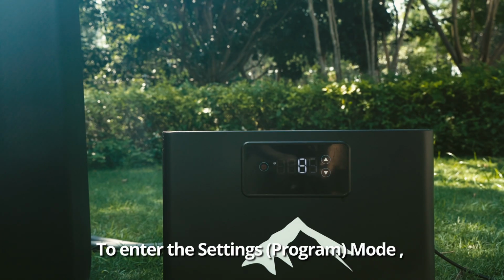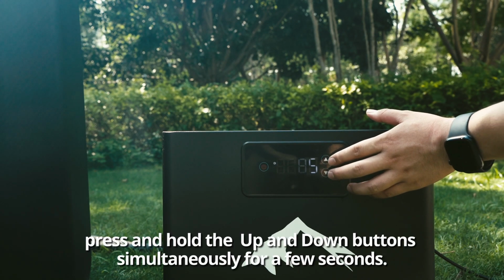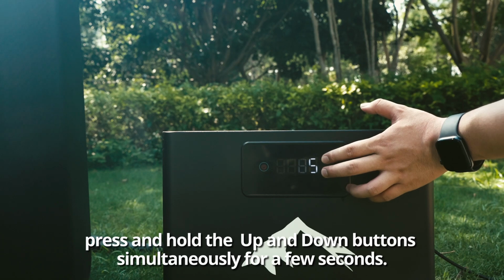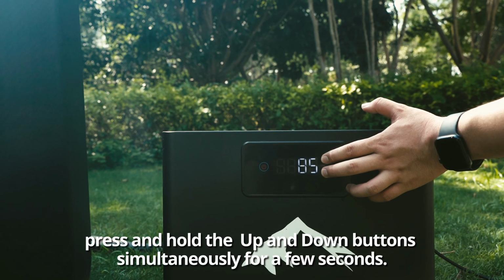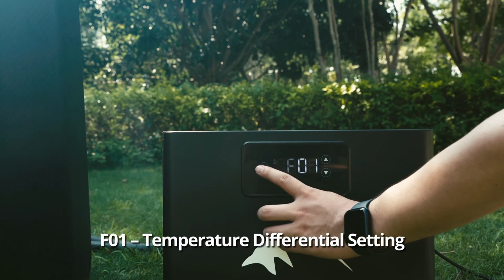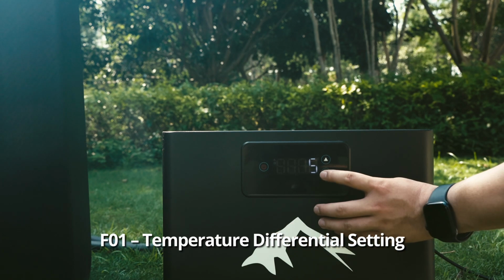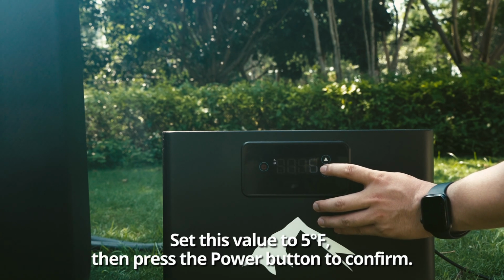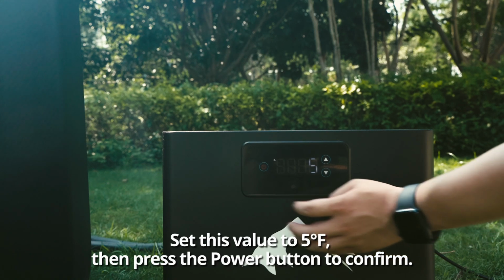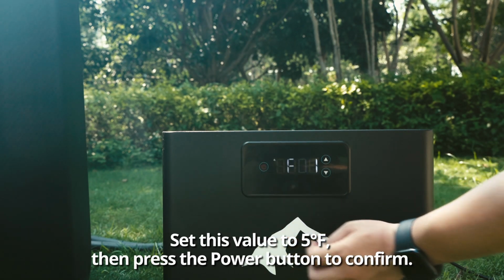To enter the settings program mode, press and hold the up and down buttons simultaneously for a few seconds. This brings up the F01 temperature differential setting. Set this value to 5 degrees Fahrenheit, then press the power button to confirm.